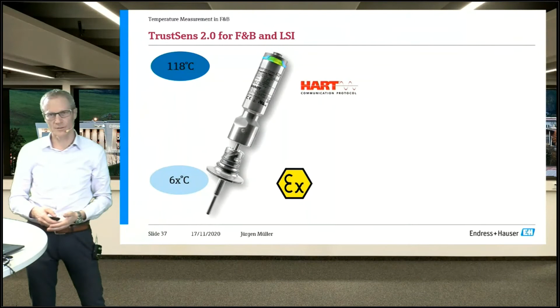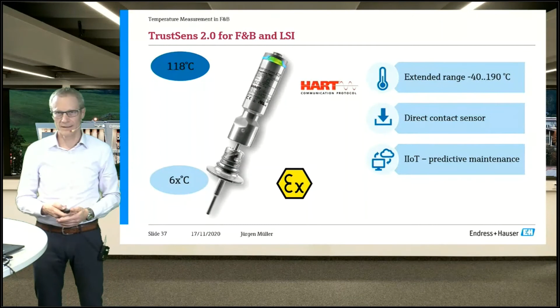The HART communication protocol is already available today, so we will offer that in future as well. And we will have the sensor with Ex approval for special applications. And also what we want to do is increase the working range of this sensor up to 190 degrees. At the moment, it is restricted to temperatures of up to 160 degrees. Then we have some requirements for some applications that you use the TrustSens without a thermowell. So we need to offer the TrustSens as a direct contact sensor. And there are more and more new requirements when it comes to IIoT features. So in this case, because we store the calibration data, we store this information in the instrument, we can use this information to give advices for predictive maintenance and stuff like that.